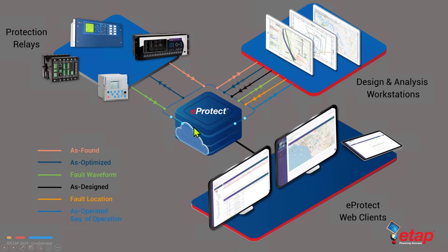This fault location information can then also be sent over to ETAP OMS that is used for essentially crew dispatch as well as outage restoration. You can also send the sequence of operation to the design and analysis workstation, and using the fault that is simulated inside the program, you can then use the sequence of operation from the as-operated system and compare it with the sequence of operation in the as-designed or as-intended system. And you can then determine whether your system protection schemes are operating effectively or not. All of this information is accessible through eProtect web clients that allow you to visualize and interact with the data using a web browser or a tablet.